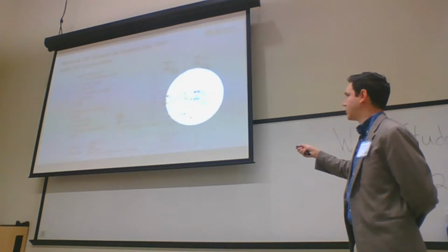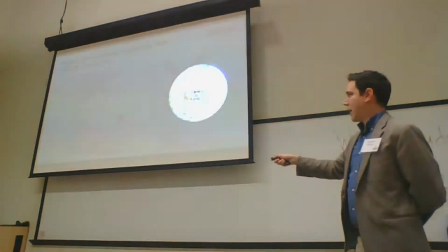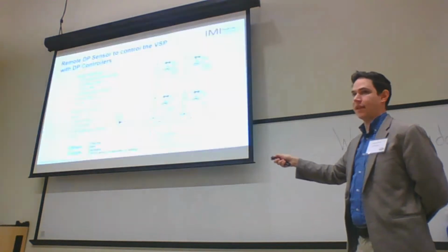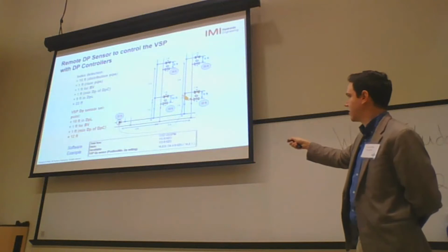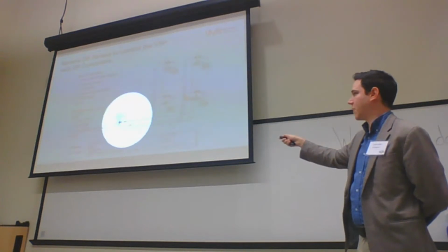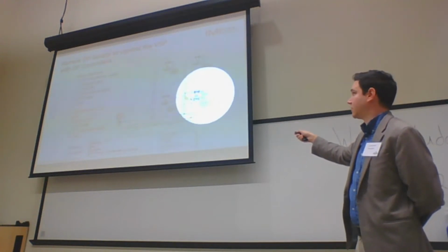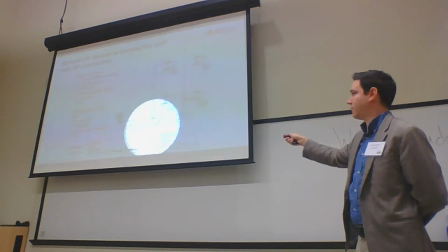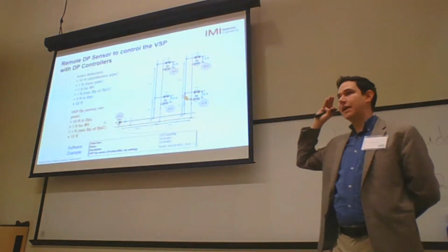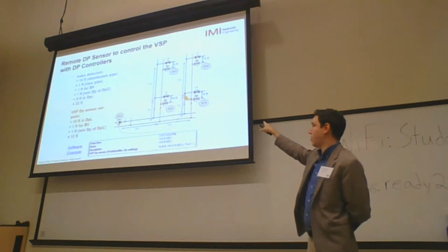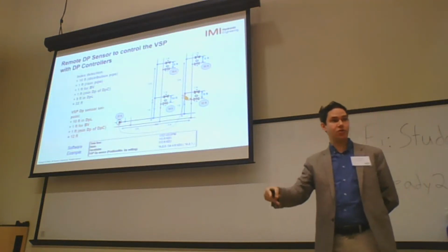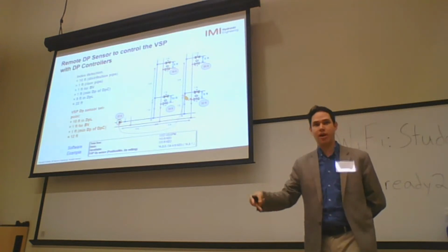So in this example, I have my 4 branches with the 4 differential pressure controllers. My pump head is 22 feet. These gray balloons are a calculation of the available pressure that I need for each of my branches. This one is 22 feet. This one is 20, 16, 18. So my pump head needs to be 22 feet because it's the highest one. I got 22 feet by summing 9 plus 1 plus 1 plus 1 plus 5 plus 5. So I know that my index path, or index branch, is the bottom right one. That's where I place my DP sensor to control my pump head, because this is my index branch.